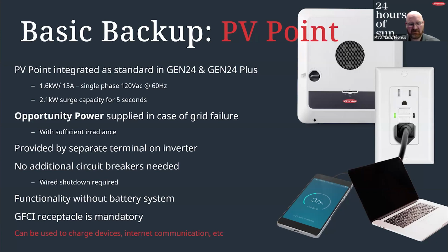So if a customer doesn't have the money to get batteries right out of the gate, they can go ahead and opt to have a GFCI outlet installed to the PV Point terminal, and it'll offer this. It's kind of a stopgap between battery and just a standard grid tie. The requirement for that is, again, a GFCI receptacle and the wired shutdown initiator if rapid shutdown is necessary.